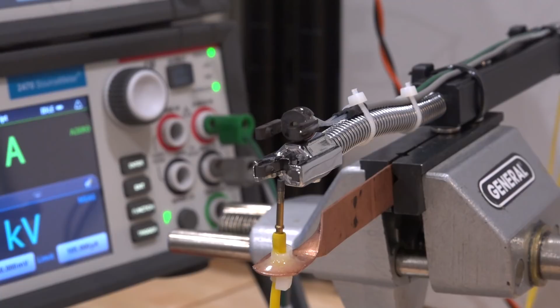Now once I do that, I have another set of electrodes at the very top that I can measure the resistance across. I can apply a very large voltage, let's say 750 or 1000 volts, and if there is a flame present between these two nodes, the resistance will drop significantly. Because of the ionized particles in the flame, it has quite a bit lower resistance than just air. And if the measurement tells me that the flame has gone out, I can activate the arc generator using the 2450 and reignite the flame. So basically like a safety system to make sure that if the flame has ever gone out, it is reignited so that there is no gas escaping in the environment.